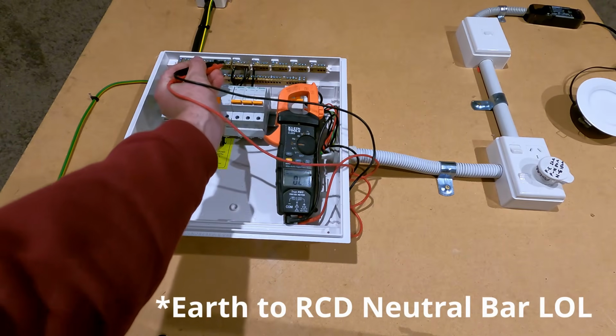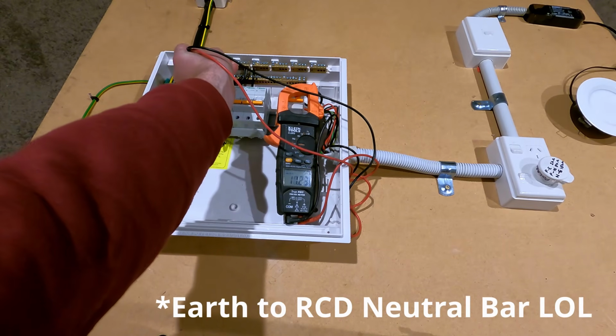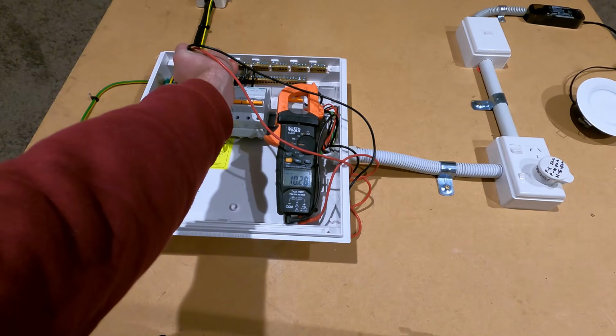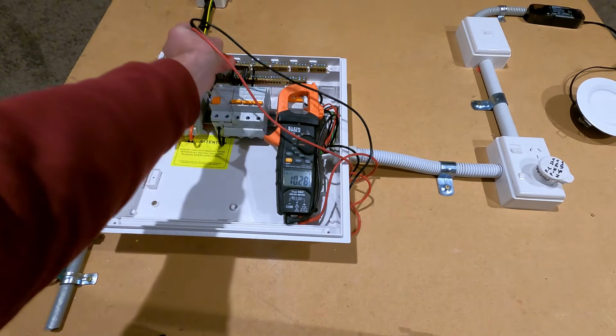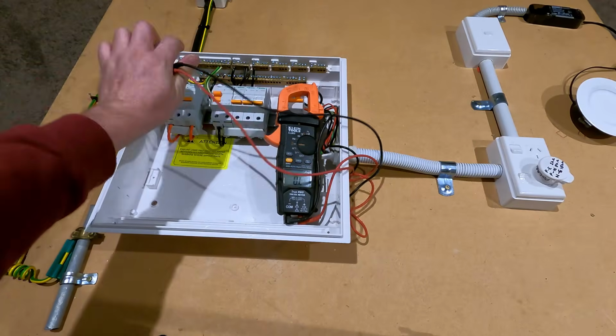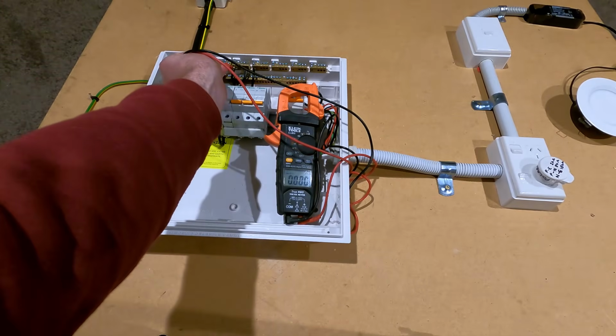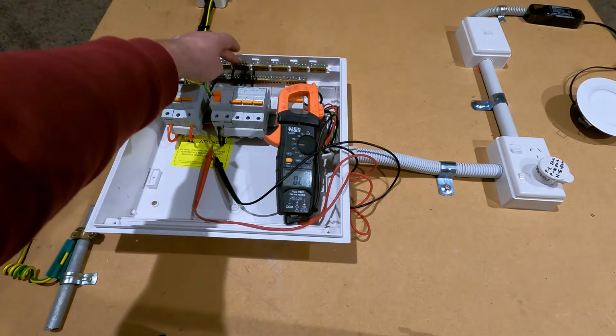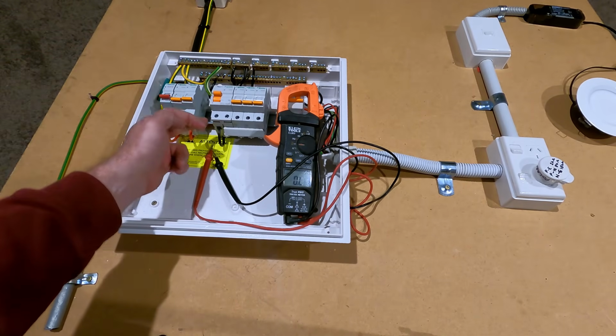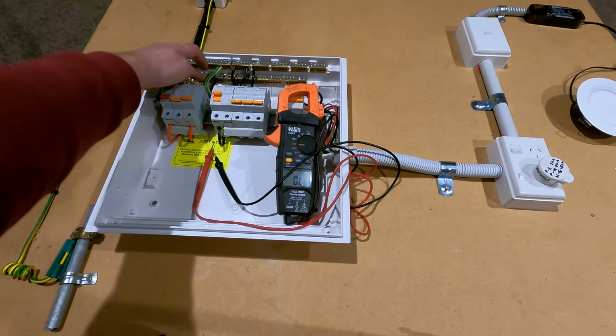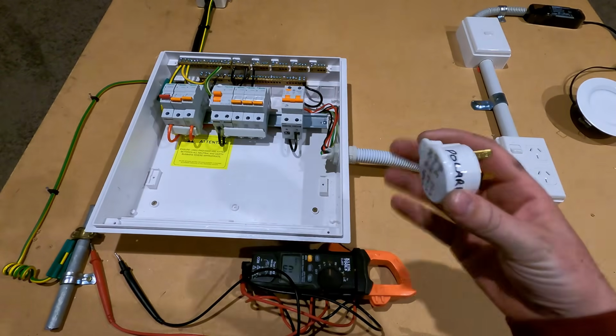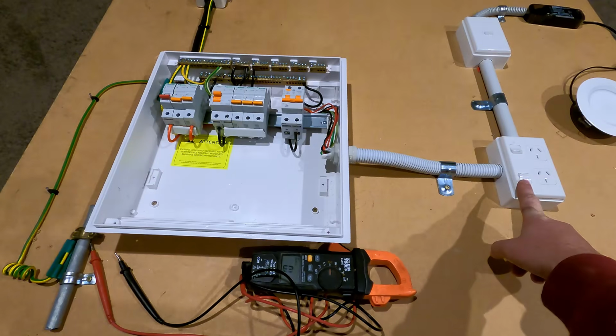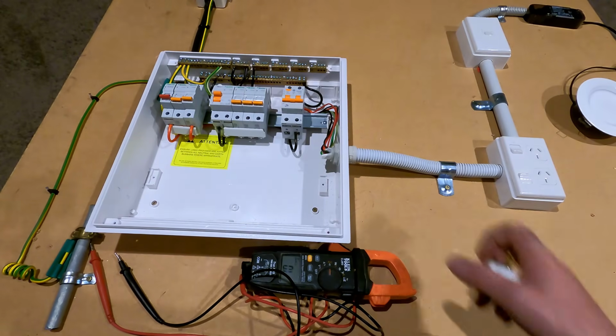And then the last one is earth to your RCD neutral bar, and that's 10 kilo ohms. So that matches up with that. Now if you accidentally had the RCD turned on, you'll see it's dead short. And that's because this RCD neutral bar is running back through the RCD, through the MEN link to the earth bar. The other thing with this is you've got to make sure that the switch mech is turned on, or your results are going to be stuffed.